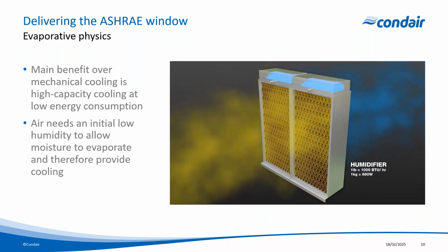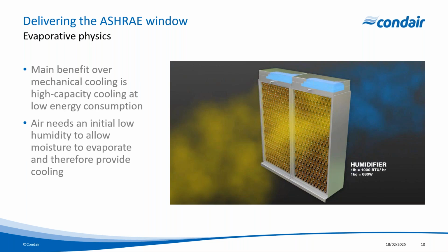So the main benefit to adiabatic cooling over traditional mechanical cooling is the ability to really provide a significant amount of cooling at an extremely low energy consumption. So the only energy that we're using here is already in the air. We're not using any additional mechanical cooling equipment. And to put this into perspective for you, to evaporate 1 kilogram of water requires 680 watts of energy. So that's the amount of energy that we need to drive that phase change from liquid water to gas.